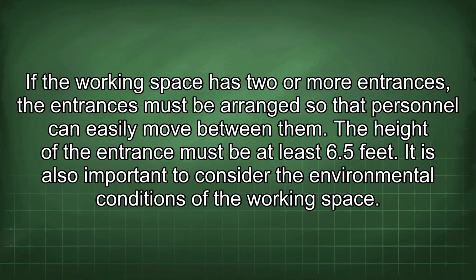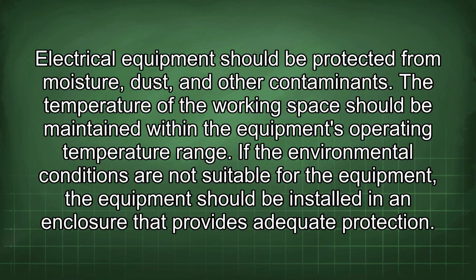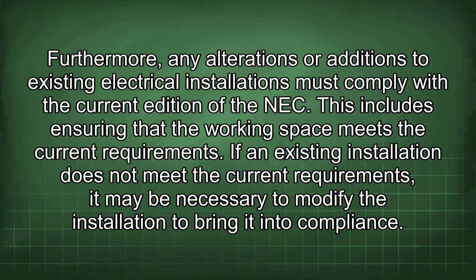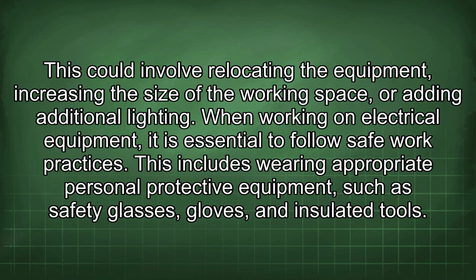It is also important to consider the environmental conditions of the working space. Electrical equipment should be protected from moisture, dust, and other contaminants. The temperature of the working space should be maintained within the equipment's operating temperature range. If the environmental conditions are not suitable, the equipment should be installed in an enclosure that provides adequate protection. Furthermore, any alterations or additions to existing electrical installations must comply with the current edition of the NEC. This includes ensuring that the working space meets the current requirements. If an existing installation does not meet the current requirements, it may be necessary to modify the installation to bring it into compliance. This could involve relocating the equipment, increasing the size of the working space, or adding additional lighting.